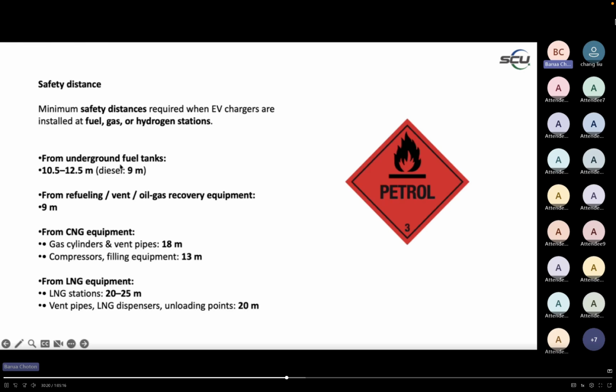From the underground fuel tanks, it needs at least 10.5 to 12.5 meters distance. So you have to install the EV chargers 10.5 to 12.5 meters away from the fuel tanks. But if it's diesel, then 9 meters is okay. From the dispenser, the vent or refueling equipment, the suggested distance is at least 9 meters.